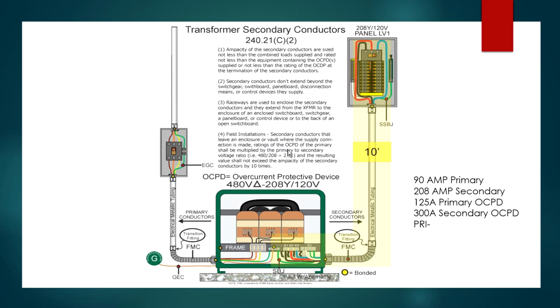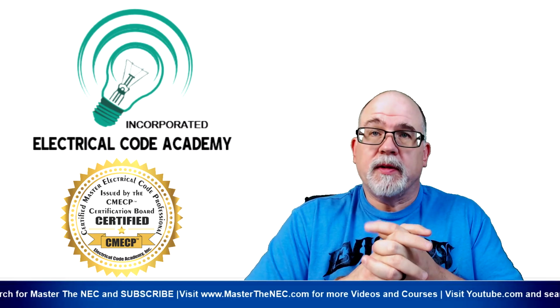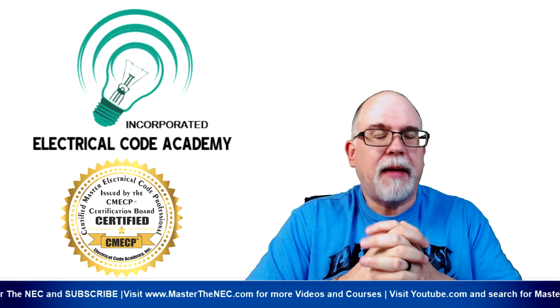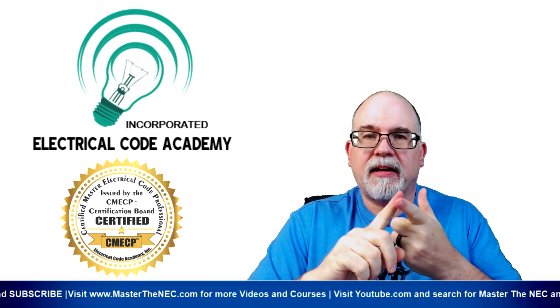Now, there might be some obscure thing that you run into. I don't have time to go over all potential issues which may come up. Just know how to do it. And I just showed you how, and that's not a problem. So if you meet 1, 2, 3, and 4, which we do here, then these conductors can go up to 10 feet. Okay. And it's not 10 foot of this raceway. It's 10 foot of the conductor. Okay. That's the 10 foot secondary conductor rule. And you're going to be fine. All right. So that's a lot of info. Overwhelming info. So again, go back and watch part 1. Learn how to calculate that primary and secondary current rating.